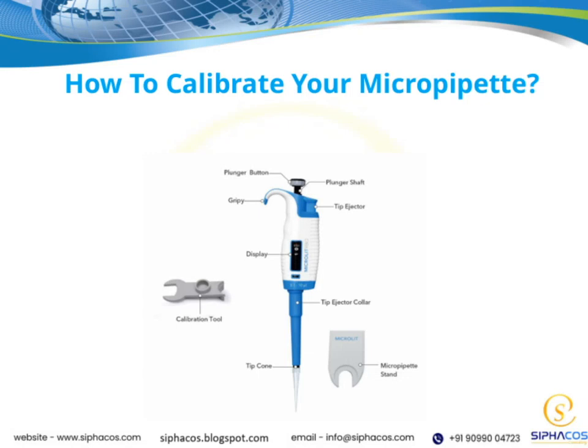So, let's talk about how to calibrate your micropipette effectively. First, it's important to understand that calibration ensures your pipette delivers accurate and precise volumes, which is essential for reliable experimental results. To start, you'll need a few tools: a balance that can measure to at least 0.1 grams, and some distilled water, since we're working with liquids. The key idea here is to compare the volume your pipette is set to dispense with the actual weight of the water delivered. Because we know the density of water, we can convert that weight into a volume, and then see how it matches your pipette setting.